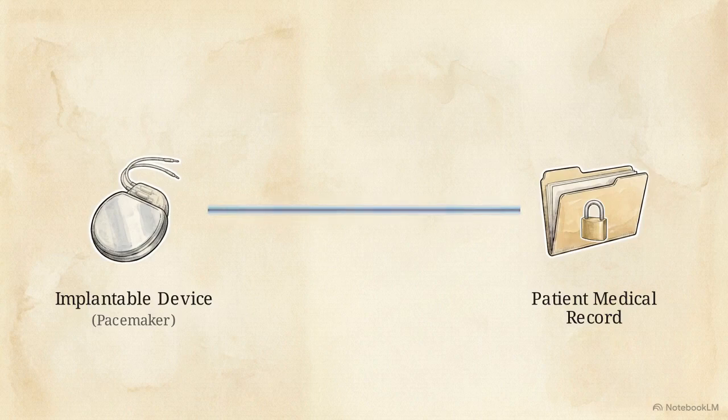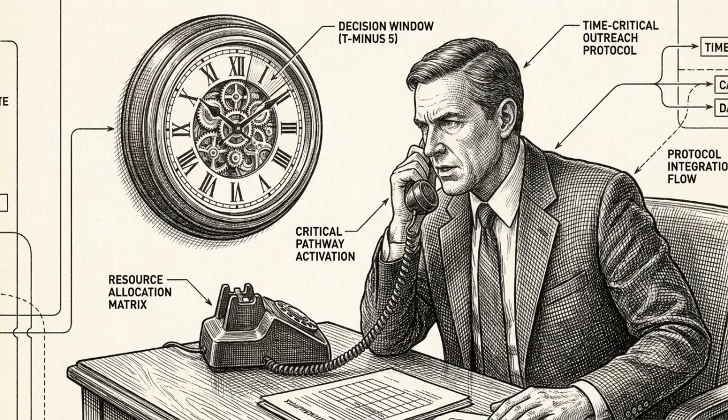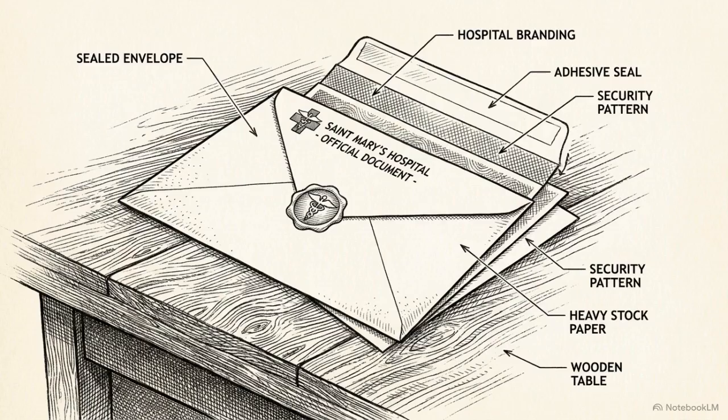Under standard ASC.04.04, the hospital must maintain this direct, unbroken UDI to patient linkage long after the surgery concludes and the patient is discharged. If the manufacturer recalls an implanted device, the hospital must use that UDI linkage to execute a patient outreach protocol within a strictly defined timeframe. Staff must contact the patient and clearly communicate the specifics of the recall, how safety surveillance will be handled moving forward, and what alternative treatments or removal procedures are available.